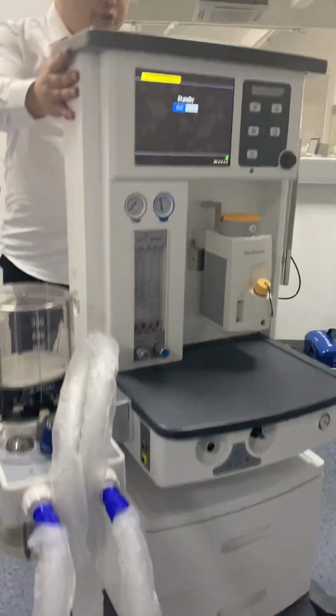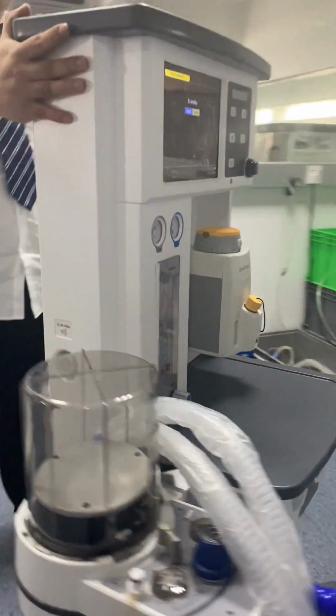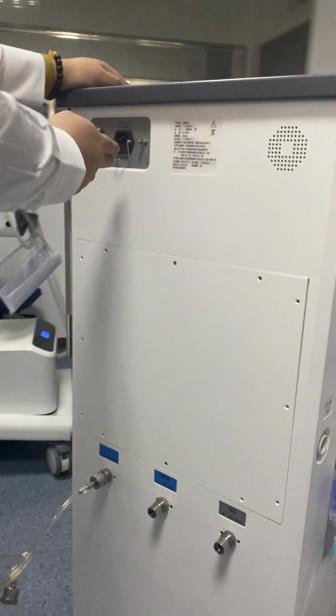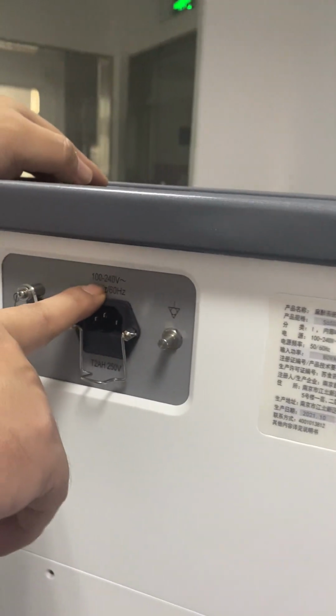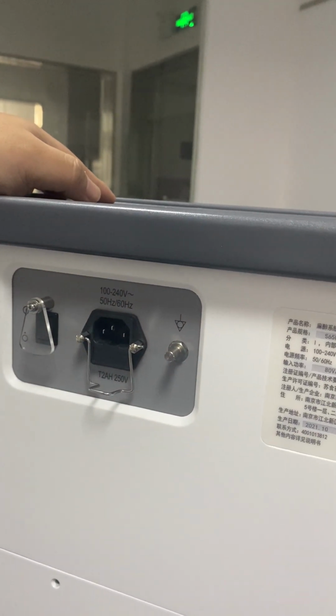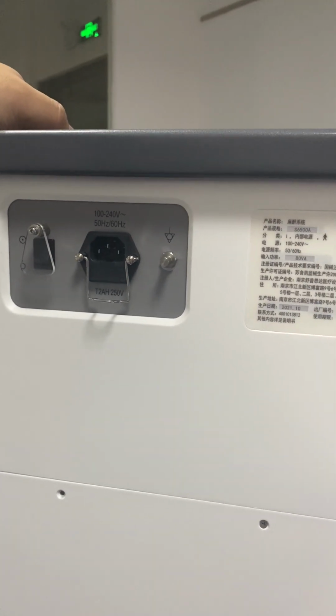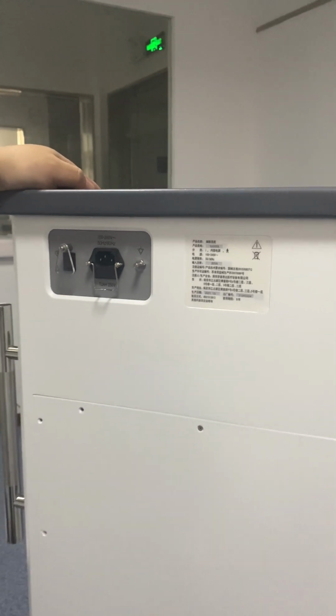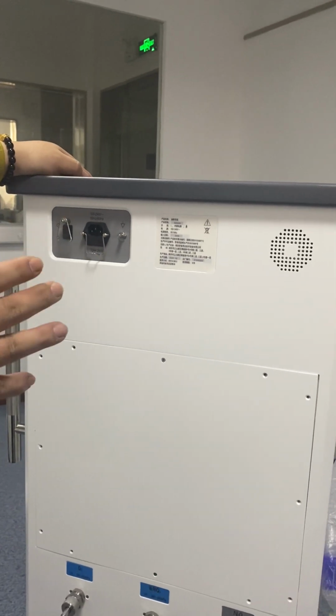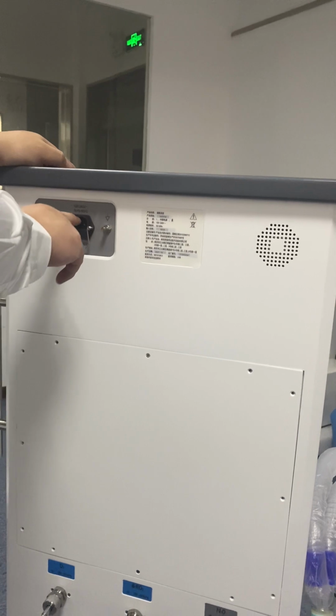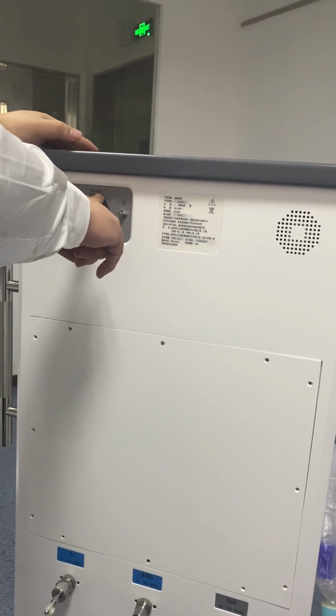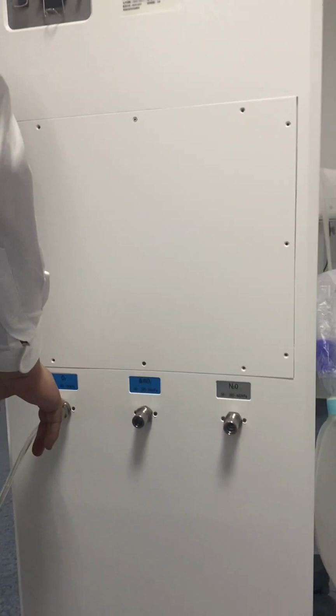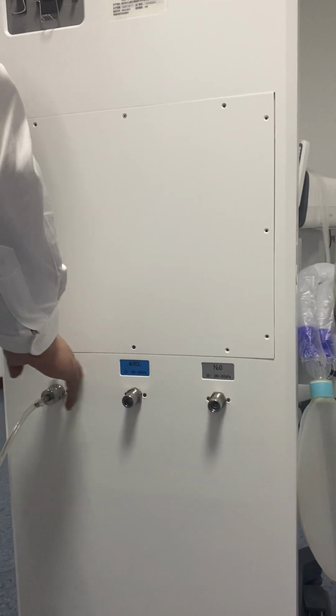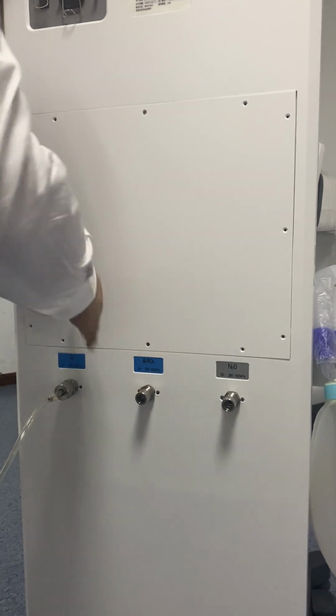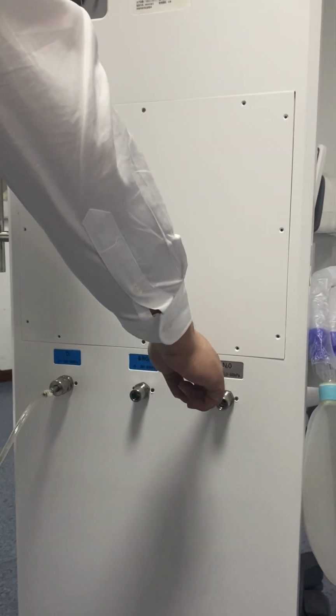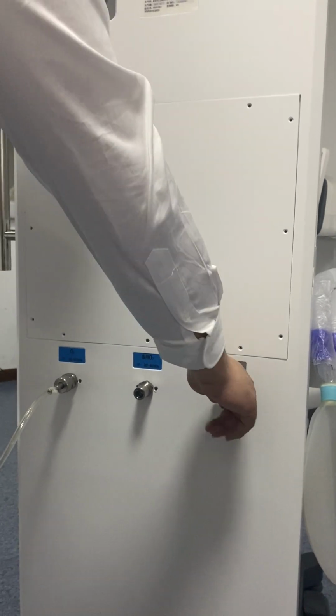Now we will see the back side of the machine. You can see the power voltage for this machine. It's running 100 to 240 volts. It means it's like having an AVR inside this machine. So no matter which country you are using the machine in, even if your local voltage is not very stable, we can still use our machine very stably because it's a wide voltage range. Here is the port. Like I mentioned at the beginning of this video, there are 2 gas sources: oxygen, because it's the driving gas, and another one for nitrous oxide, or if you choose air, then it will be air.